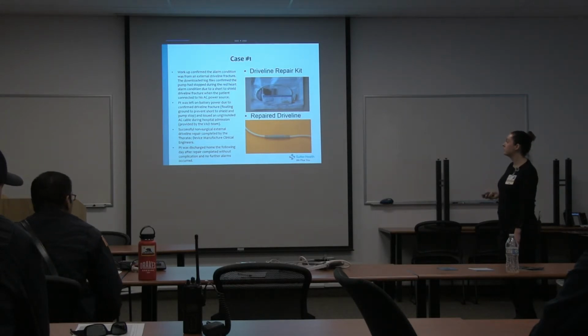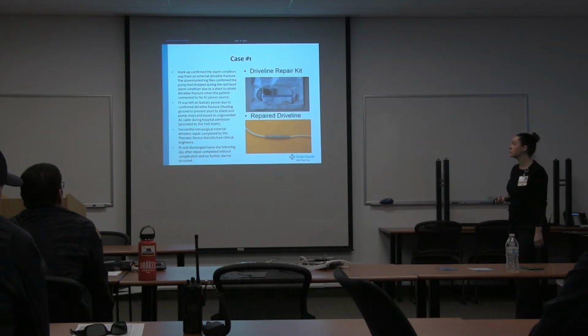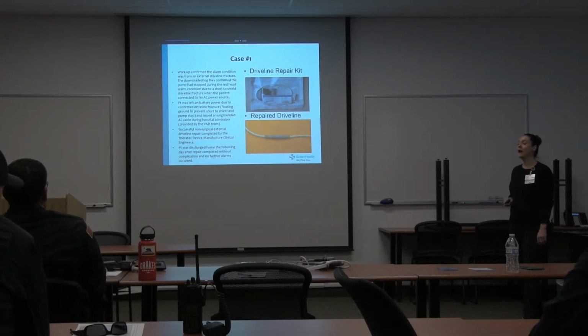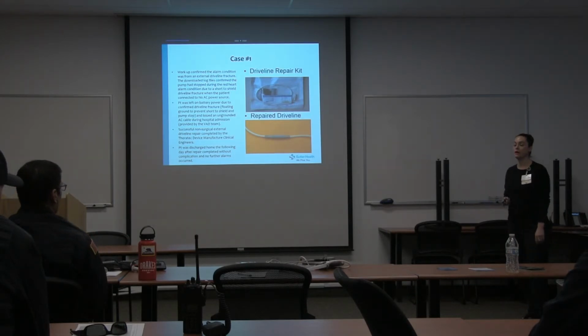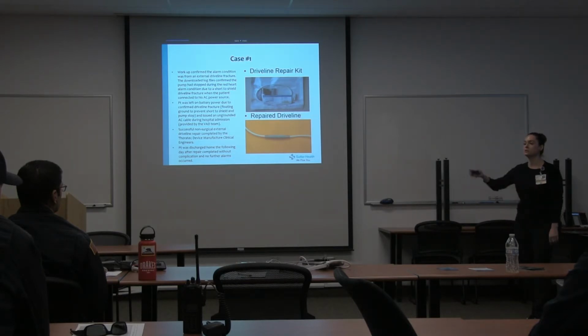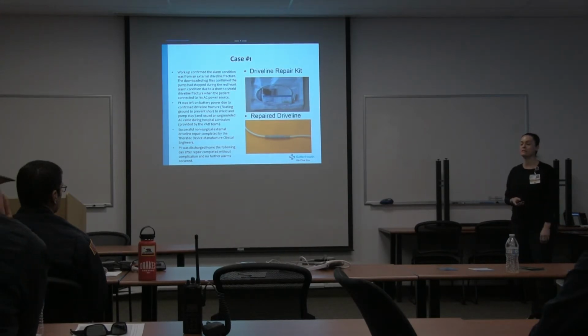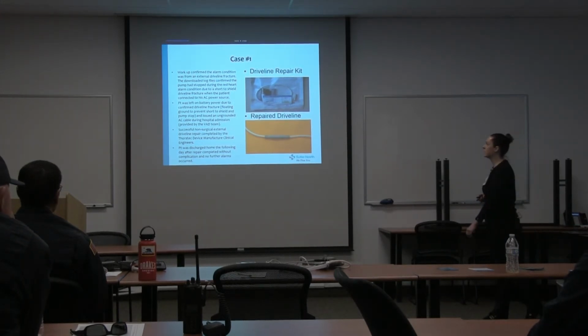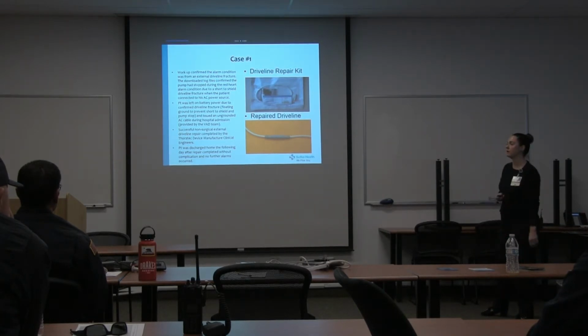So we did a workup, confirmed the alarm condition was from an external driveline fracture. What happened was he connected himself to the wall and it shorted out his pump, because when you connect to the wall, it grounds out. So this gets into the real electrical engineering portion of these pumps, and that's why it's helpful to have us on call to be able to troubleshoot that with you guys and tell them, get them off that wall source, get them on batteries, keep them on batteries, because the pump will run on batteries.